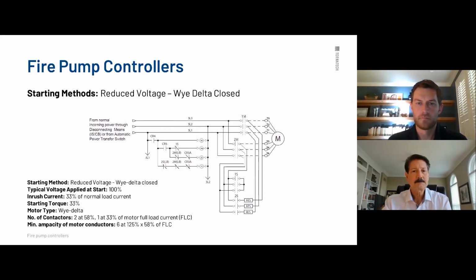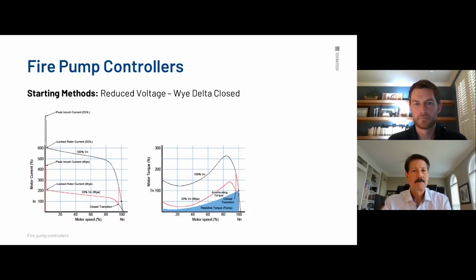By having a closed transition, you see we could look at 2, 2.5, maybe a little 3. We have, again, peak inrush, which is negligible, but this is very, very nice inrush on startup. And as you increase to about 85 to 90% speed, you see there's a little blip here. That's going from reduced voltage to full voltage. And by having those resistors in line, we continually have voltage across the motor leads 100% of the time. That's crucial. That's the closed transition. And I'll show you the reason why on open.